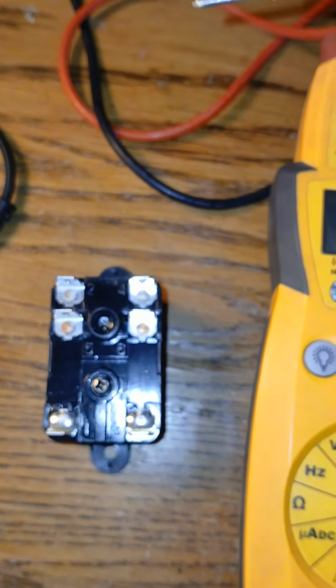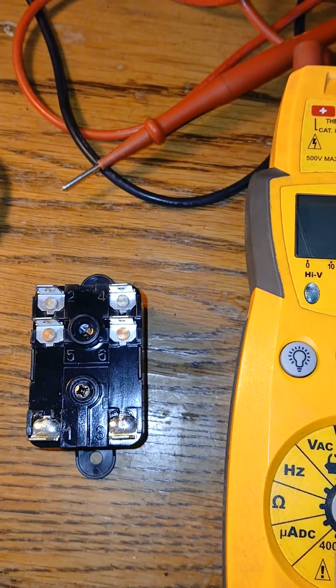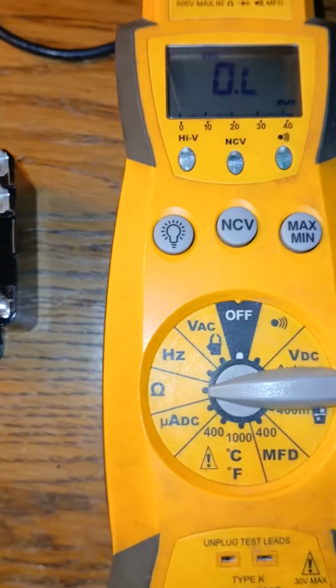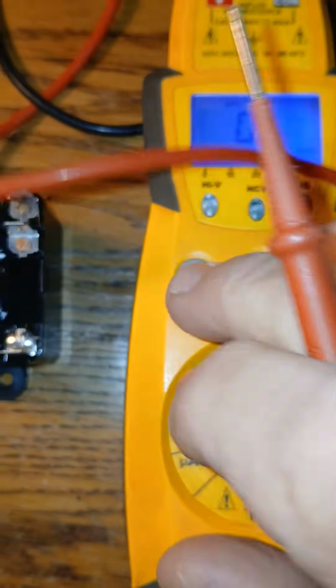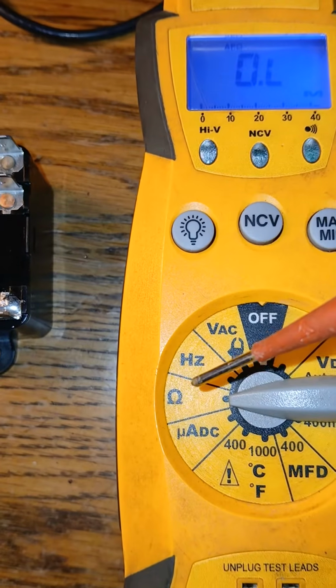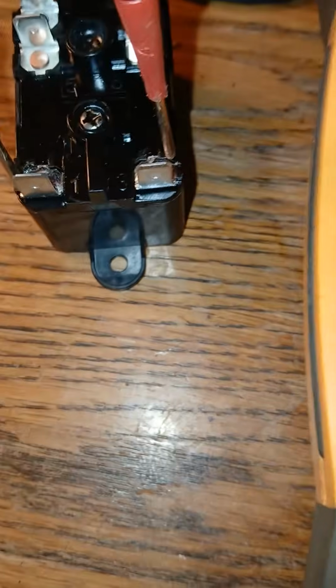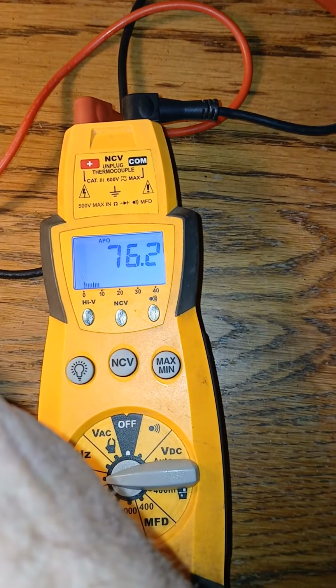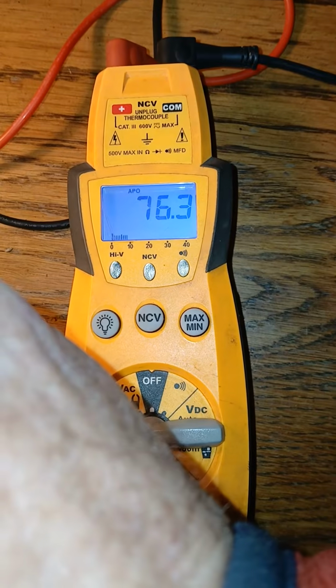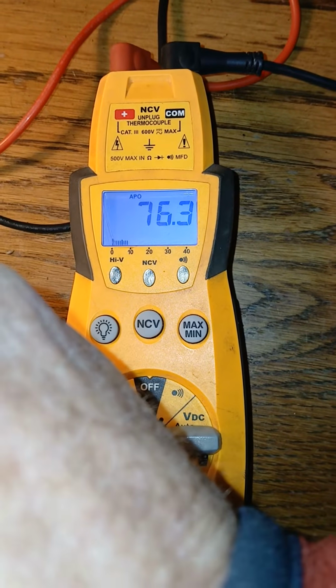So if we want to test this thing, the test is we put the meter in ohms. So we flip it to ohms. Now we're in ohms mode. Turn the light on just to get my kicks. As one can see, it's this little horseshoe looking thing here. Now we're at OL. If we put the probes here, we should be reading between 70 and 80 ohms. This should be on the low voltage side. Now we're at 76.3. Again, 76.3. 70 to 80 means it's good.